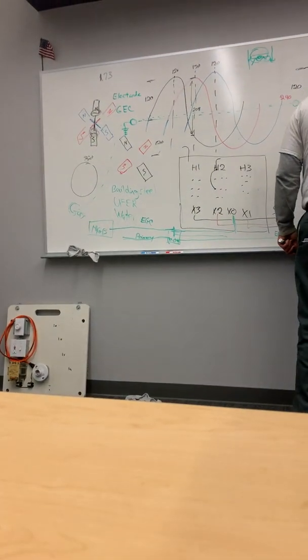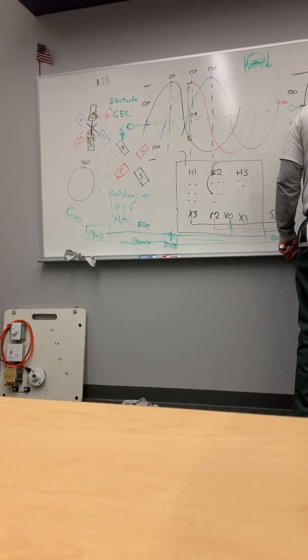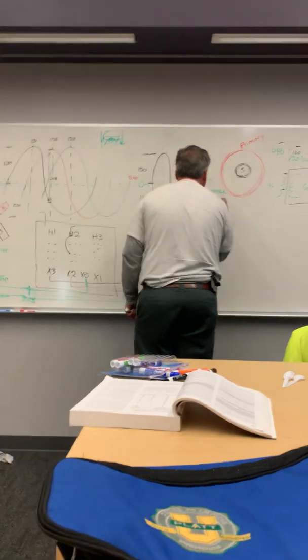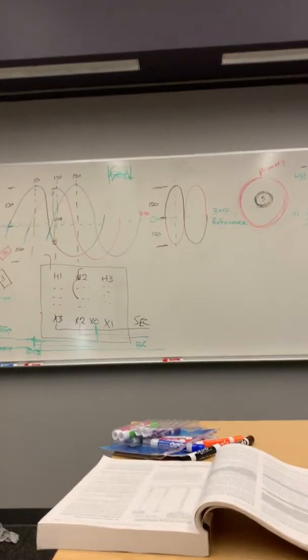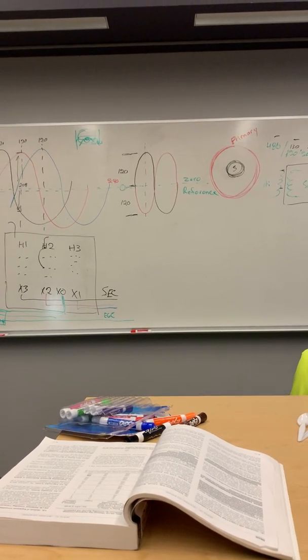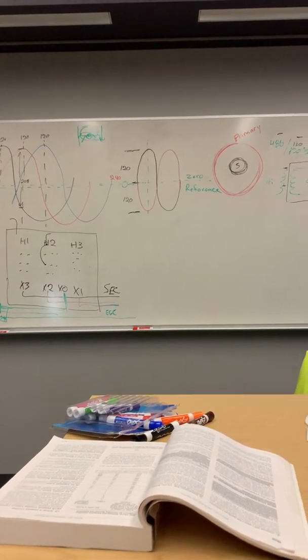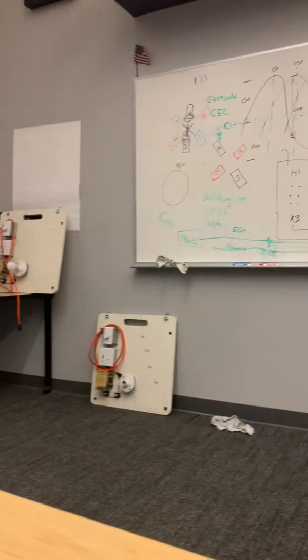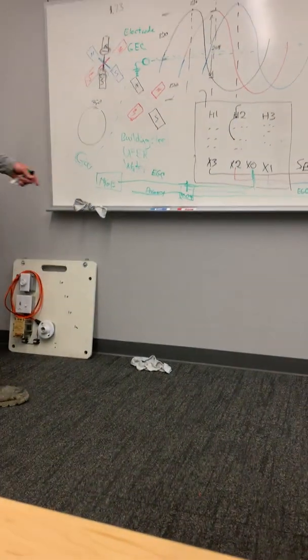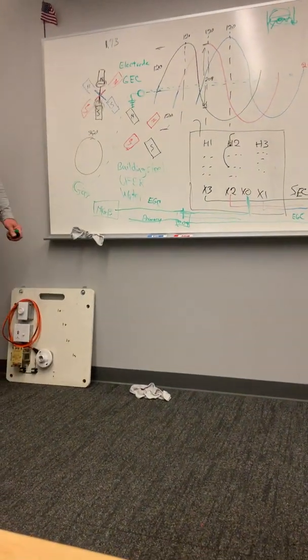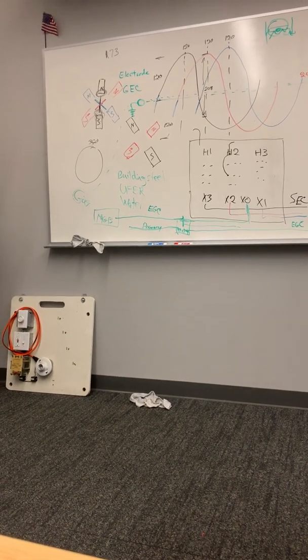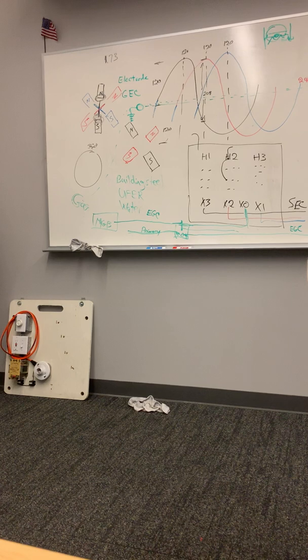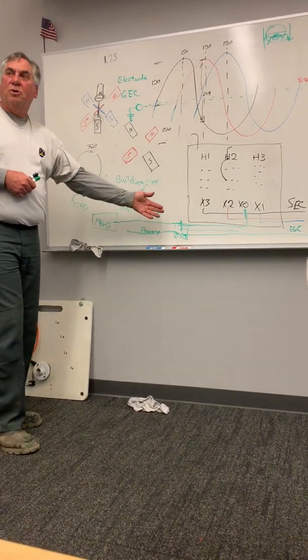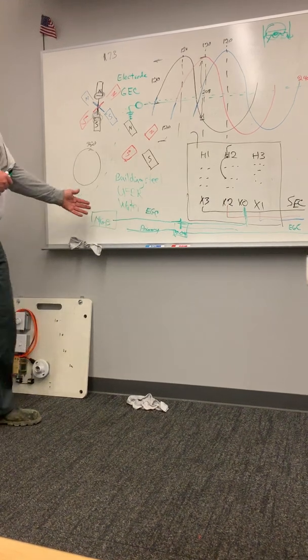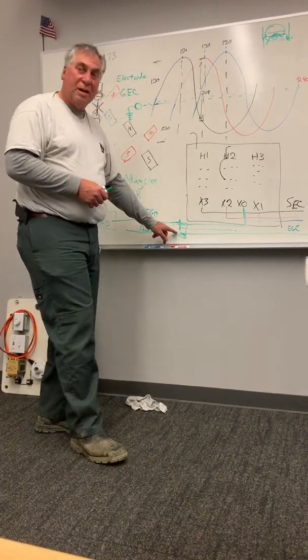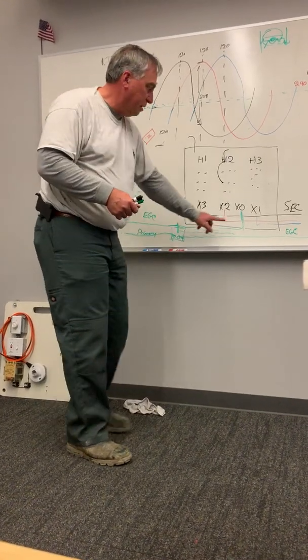Do we trim it, or go around it and then tie it in? You know how you trim it, go around it? Yeah, expose it and then put it in. You just peel back the insulation and run it through there, and I call it a beaver tooth. I don't know why, that's just what I always call it. Now, the technical word, I think, is a lay-in lug. You just don't have to break it. Because the point is I want to keep that low impedance path. I don't want it to go through this mechanical connection and this mechanical connection. I just want it to be a solid piece all the way here.